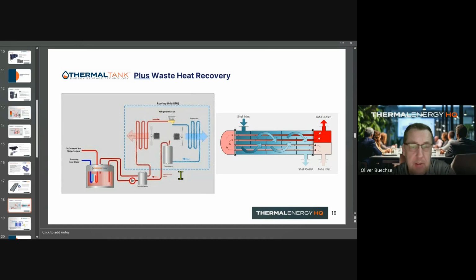In breweries, in laundries, a lot of hot water goes down the drain, literally. And these systems allow a percentage of that waste energy to be recovered, put back in the tank as the storage medium, and then be used again. And that really changes the energy equation dramatically, because in this case, your incoming water is not going to come in at whatever the ambient temperature is, say, 55 degrees Fahrenheit, but it might already come in at 99 degrees Fahrenheit. So a heat pump or whatever other heat source you have that sits on the back end of that has far less work to do to get it to the target temperature where it re-enters the process.